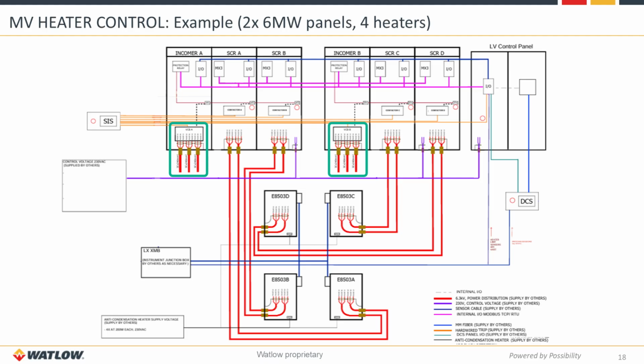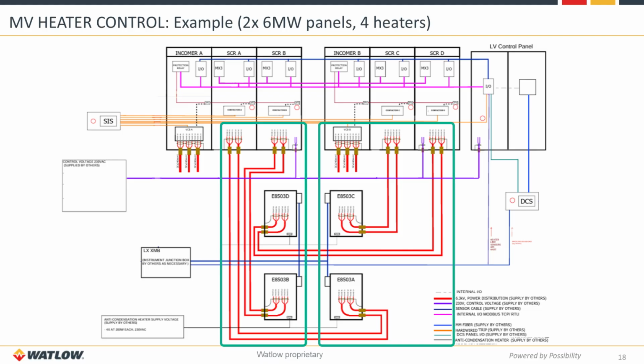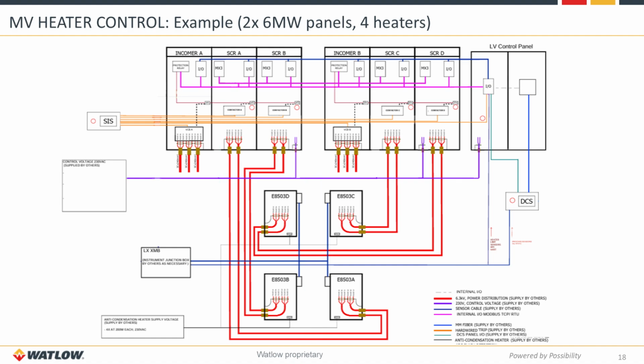So a single power line coming into the incomer that has a vacuum circuit breaker associated with it. The power is then distributed amongst the panels, and then the output power here goes over to each one of the heater enclosures for powering each one of the heaters. So again, a fully integrated system, lots of flexibility, and a lot of ability to configure it the way you need to ensure that we're meeting your particular application.